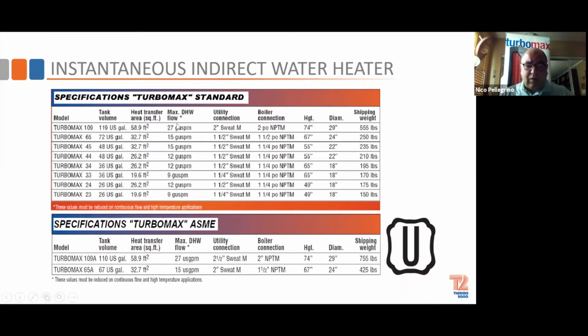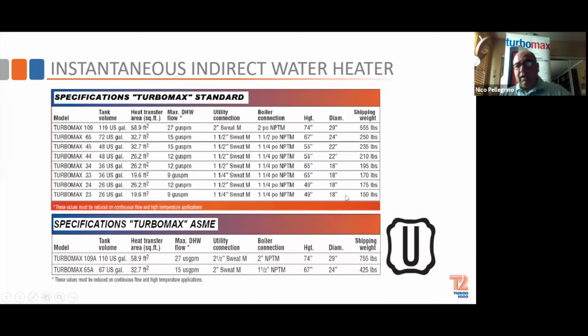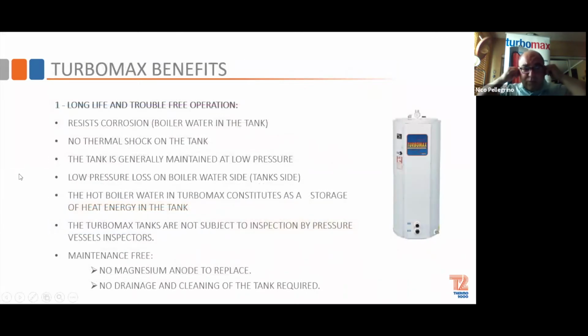But technically, the 109 is 119 gallons, and these diameters are the outside of the tank with the jacket on it. So basically, some of the benefits: it's resistant to corrosion because it's boiler water. So if your boiler water is treated and well maintained, then you're going to have a long life with the Turbomax, because there's no chance of any scale buildup. There are no magnesium anodes to replace, and there's no cleaning of the tank due to pressure vessel inspections, because we're not storing domestic water.